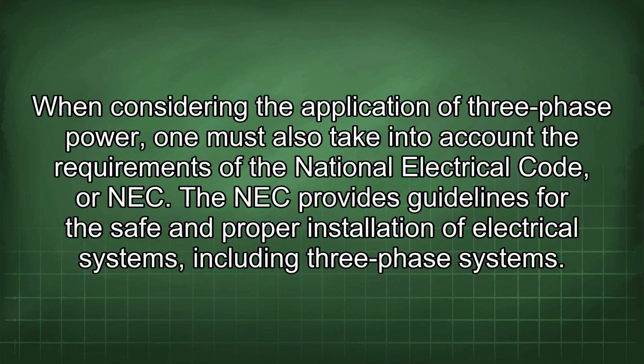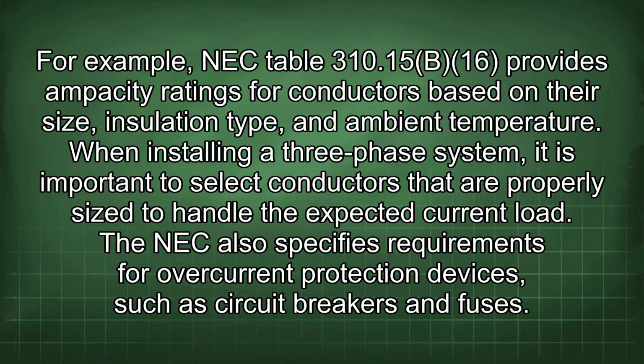When considering the application of three-phase power, one must also take into account the requirements of the National Electrical Code, or NEC. The NEC provides guidelines for the safe and proper installation of electrical systems, including three-phase systems. For example, NEC Table 310.15(B)(16) provides ampacity ratings for conductors based on their size, insulation type, and ambient temperature.